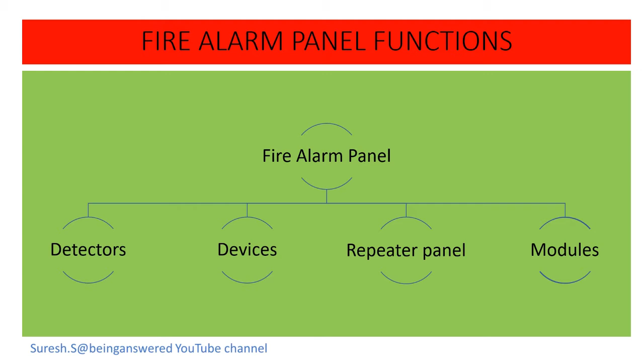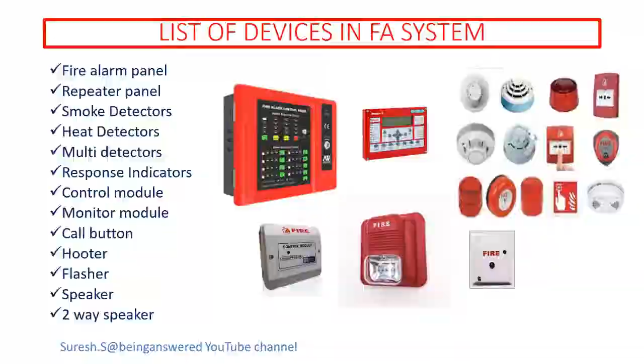Let us see the basic components of fire alarm system: control panel, communication cables, sensing devices, notification devices, and integration components. Let us see the functions of fire alarm panel. It is a microprocessor based control panel which manages the detectors by receiving the live updates and sending the information to the announcement device. Third-party integration for monitoring and controlling will be done by using control modules, and for easier usage, repeater panel will be added in the circuit to duplicate the main panel info, so that the 24/7 security service team can have the access on the repeater panel to address the issue immediately.